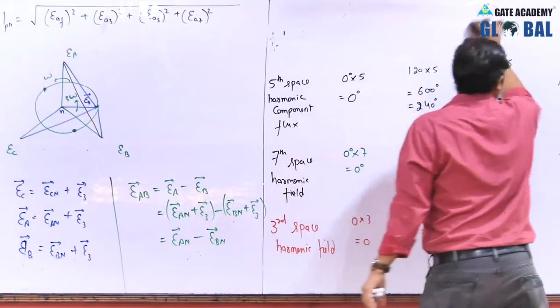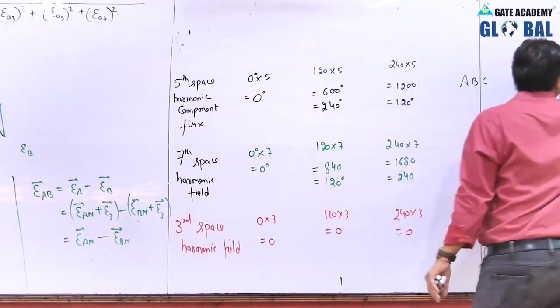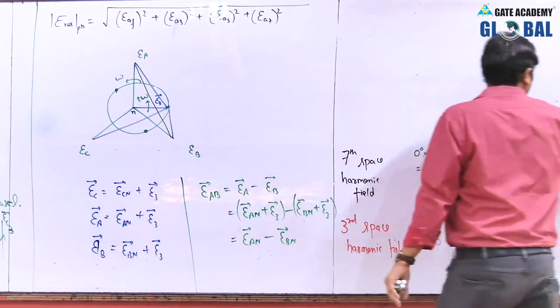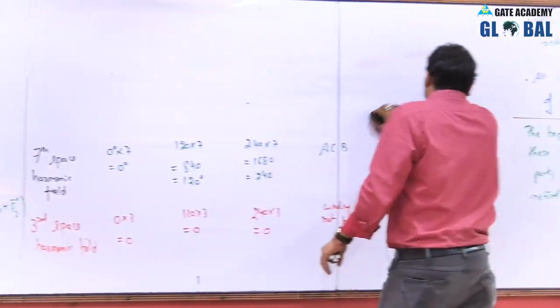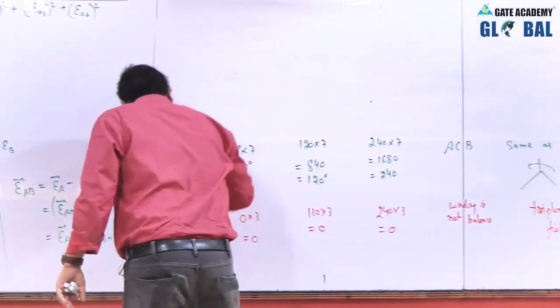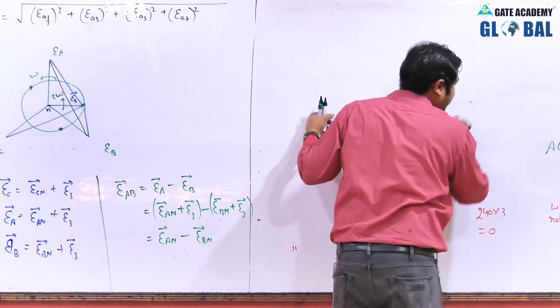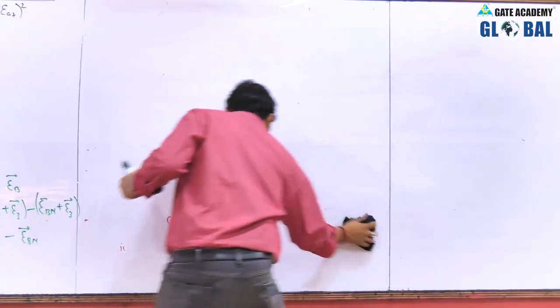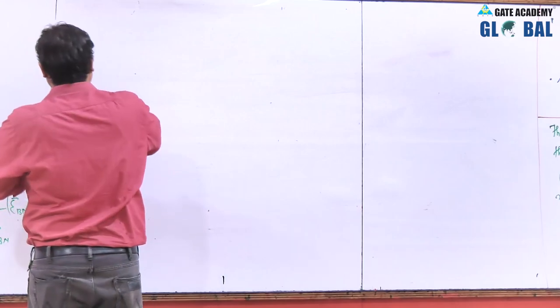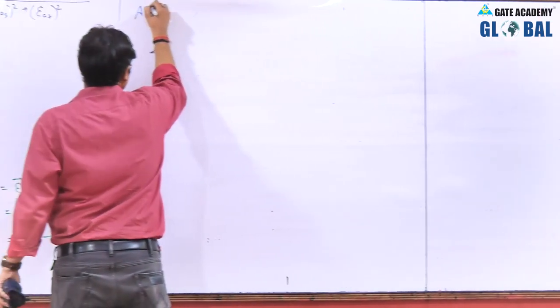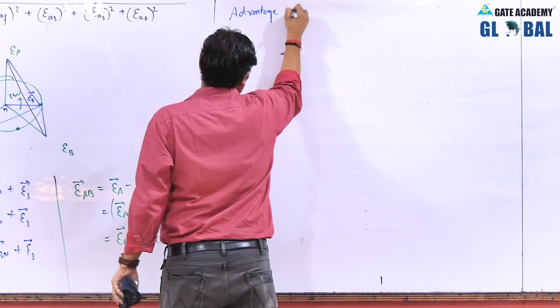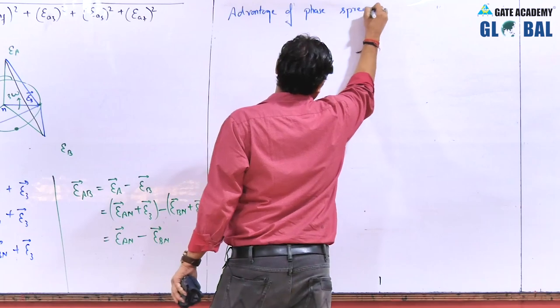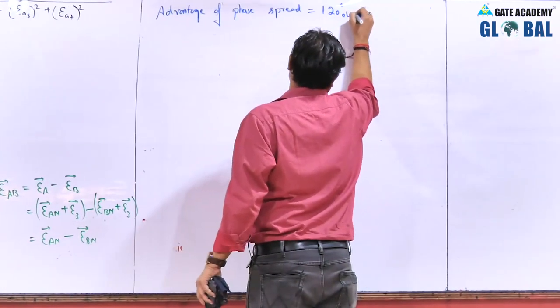The triplen harmonics are dangerous because with them mixed loading is not going to be possible. However, if we design the phase spread to be 120 degrees electrical — which is only possible in the case of double layer winding — then all triplen harmonics can be avoided. The advantage of phase spread equals 120 degrees electrical is now discussed.